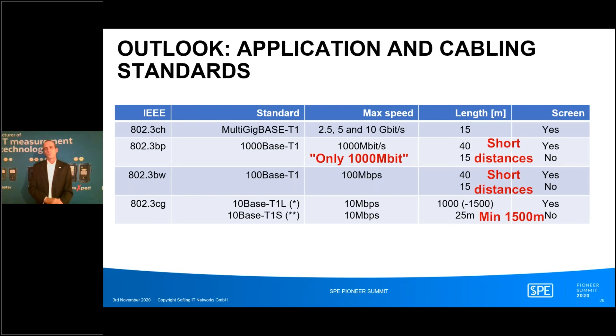Another open question I mentioned before is point to multipoint applications — we're essentially back at bus structures for Ethernet. How would you test that? If you just connect your tester to the very ends of the bus, you have a lot of open connections, and those opens give you a lot of reflections back, so that test would certainly fail. This is not an option — it won't work.